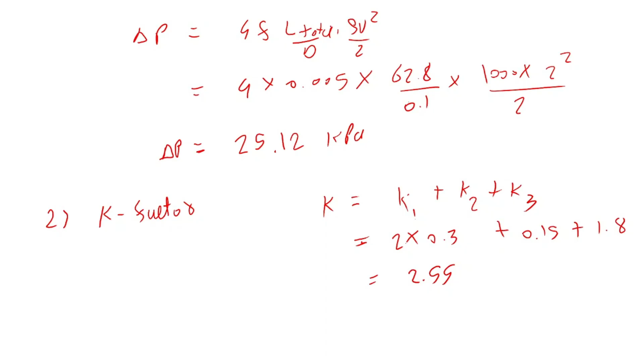Now the second method is the K method, right? The K factor method. So again, K total we can compute for all fittings, the summation of K1, K2, K3. This is given as 0.3, 0.15 and 1.8, right? So we have two elbows, so 2 times 0.3, plus 0.15 and 1.8, so 2.55.